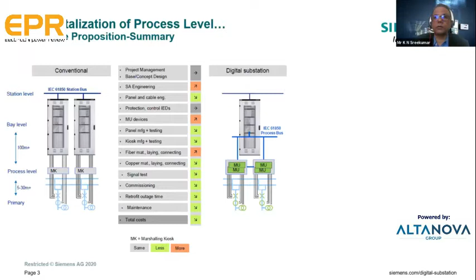What's shown in light green becomes less in a digital substation—much less copper is used, but a little more fiber cable for Ethernet connections in and around the substation. Overall, what used to be huge bunches of copper control cables inside the switch yard and protection control cubicles can be significantly reduced with this concept, which also reduces capex.